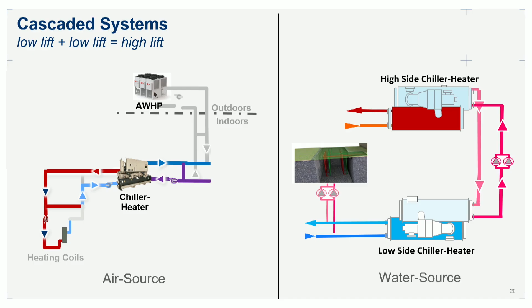But if we split that lift requirement in two - a low temp machine doing 90 degrees of lift and a high temp machine also doing 90 degrees of lift - now we're achieving our total lift, but using traditional HVAC equipment optimized and zeroed in on those operating maps. This is a very simple system diagram of what that looks like, both for an air-cooled and a water-cooled, in this case geothermal sourced, project layout.